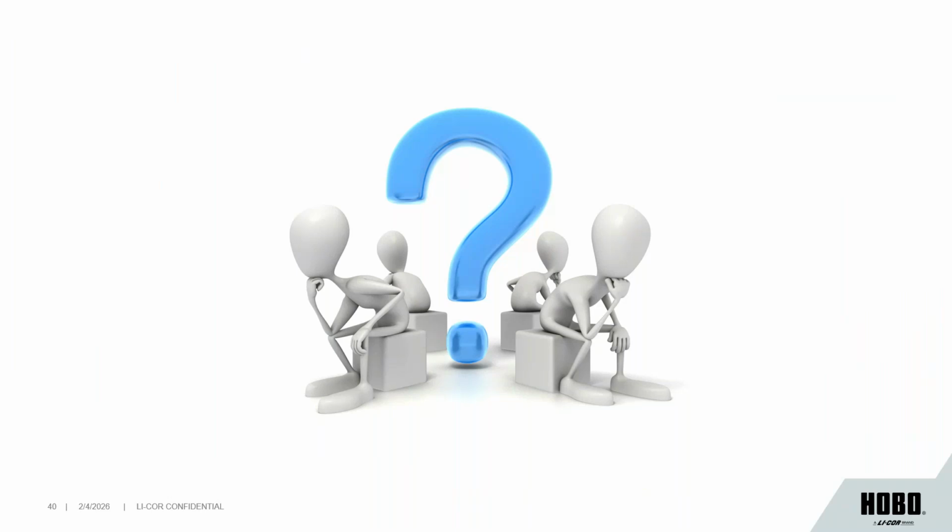Mamadou, if you don't mind, I'm just going to start rolling through some light questions because they're all tied to each other. So someone said, what happens if it rains? Do we need to use the in-water multiplier? No, we don't. If there's a little bit of rain on it, that's fine. But if it is deployed in the water, then we would definitely want to use the in-water multiplier. And the water sensor in the 2502 is not going to interpret a shower as being underwater. It's a little bit more sensitive than that.